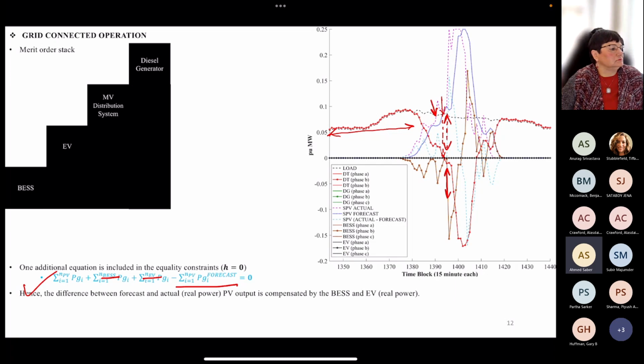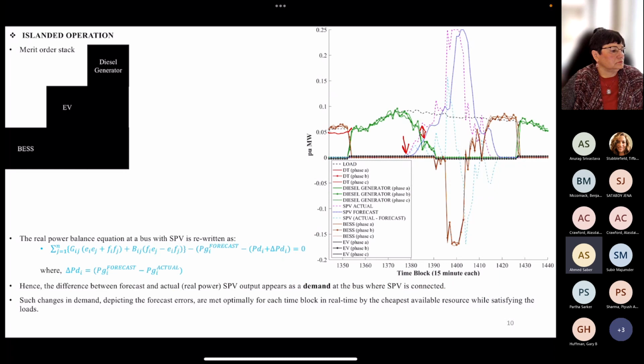The battery was for the forecasting error. It was told that you don't have that much error, so the battery can sufficiently handle that difference. So why do you need diesel again? I think you need diesel because you have other loads and your load is islanded. The diesel is needed because your system is islanded, not for the difference for solar. Exactly, sir, we use diesel only during islanded operation.